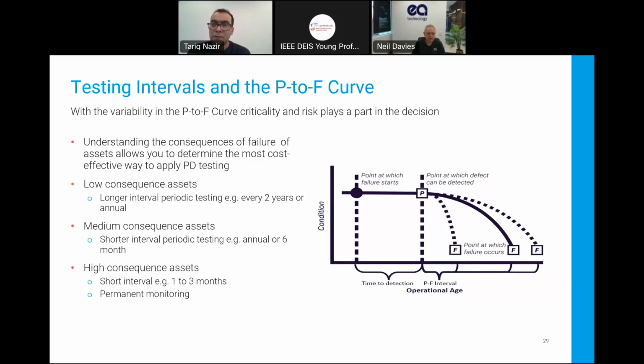Medium consequence assets, you would look for a shorter, so annual or 6 months. And if you've got high consequence assets or high risk assets, then the shorter the interval, the better. 1 to 3 months if you've got a handheld and you don't want to put permanent monitoring on, or permanent monitoring is the way to go, because that will give you that best probability of detecting all the failures.